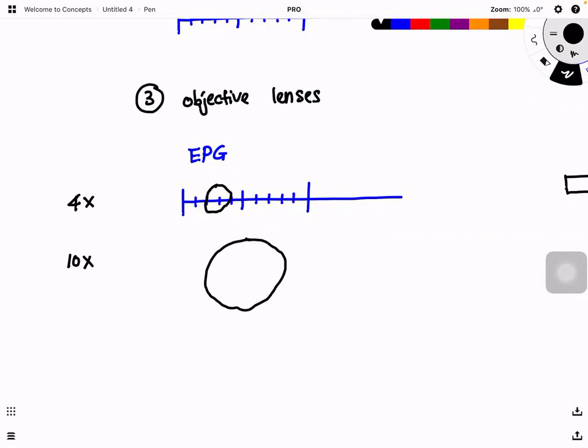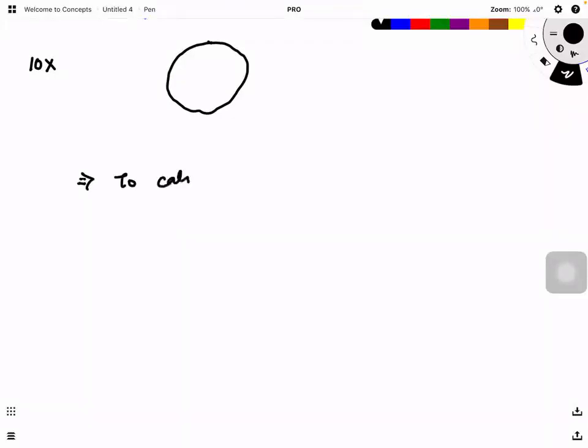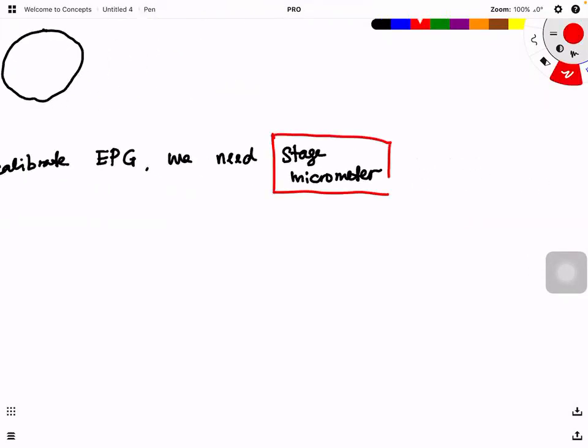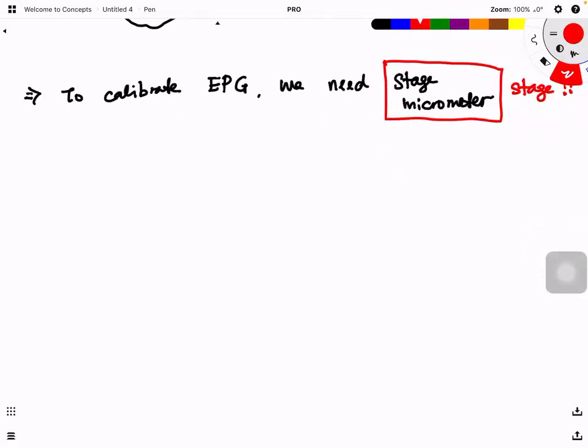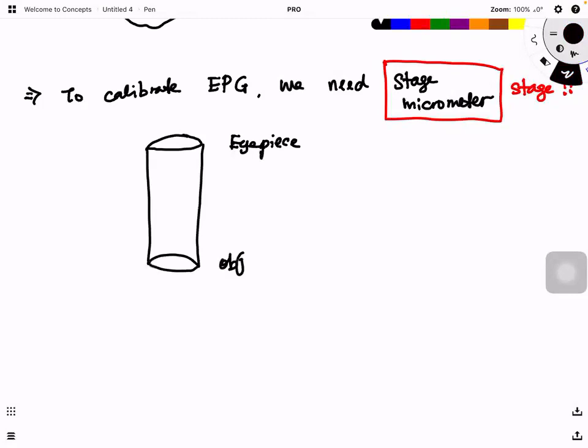So how are we going to do this? We need another item known as the stage micrometer. To calibrate the unknown ruler, you have to use an actual ruler. So to calibrate the eyepiece graticule, we need a stage micrometer. From the name, we know that we're going to place it on the stage of the microscope. Are you clear? So when you place it on the stage, look at it again. This is the eyepiece. This is the objective lens. As I said, you're going to place the eyepiece graticule somewhere here, this EPG.